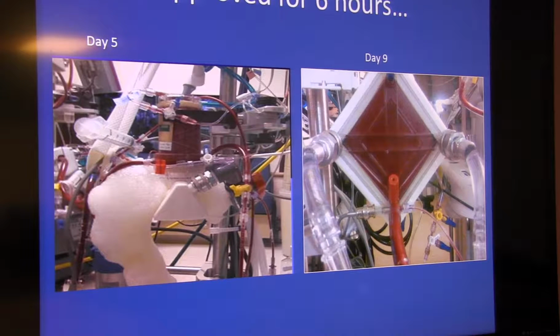Probably you said that, but this sweep speed, where does it measure? There's a flow meter right here. And where does it measure in the system? Here, it doesn't, it's just off the flow meter. You can see what the flow meter is set at, and just like you can see the FiO2. So it's just like a nasal cannula. Where are you adjusting your sweep? Okay.